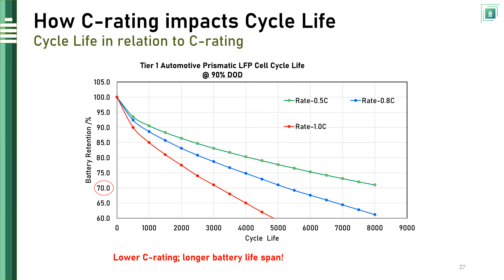The reason I mention this is some competitors will say their battery charges at a 1C rating at a really high rate. While that may be true, this slide isn't specific to Fortress Power, it's specific to batteries in general. So any manufacturer stating their battery charges at 1C, it may be true, but you won't get as many cycles out of the unit, and the battery retention rate will be much lower too.